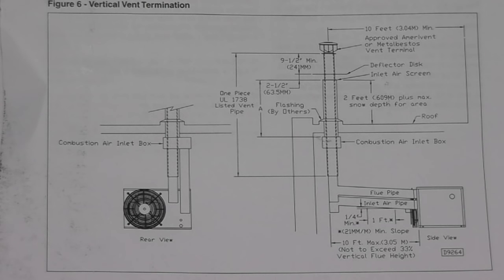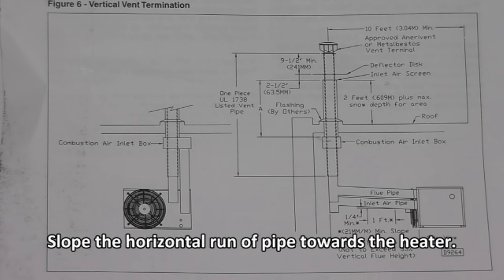Here's the vertical venting diagram. A few key items mentioned: make sure the flashing is installed, and make sure the 7-inch pipe extends 2 feet above the roof surface or the maximum snow depth in your local area, whichever is greater. Also, you have to slope the horizontal runs of pipe a quarter inch per foot towards the heater.